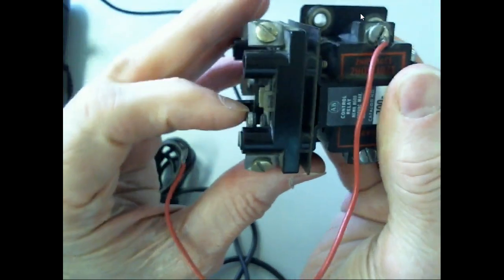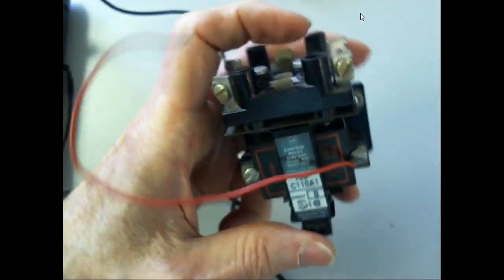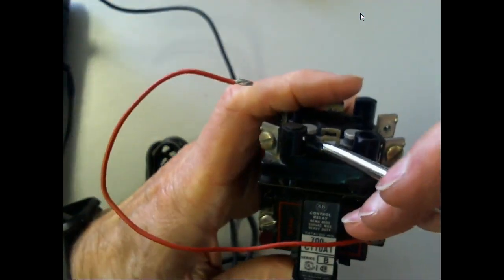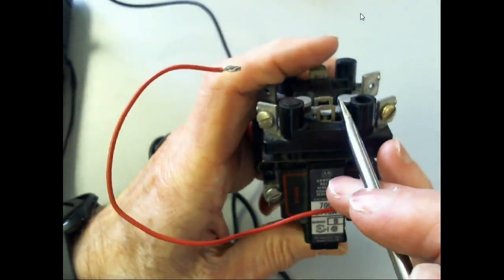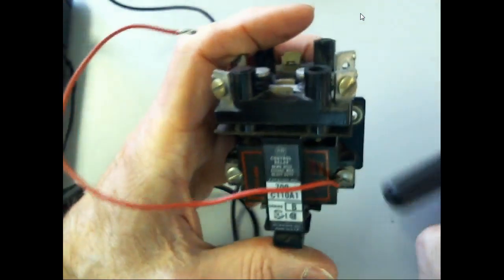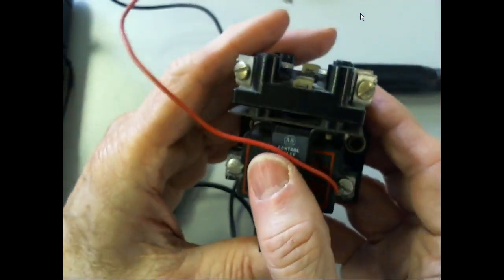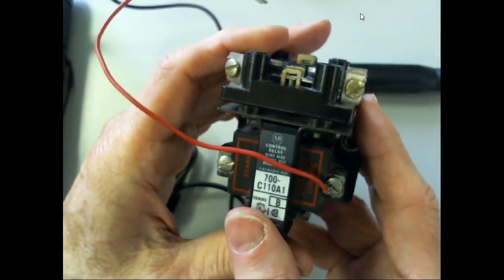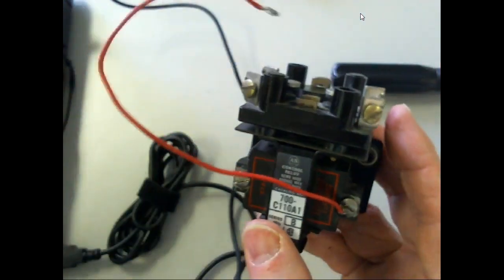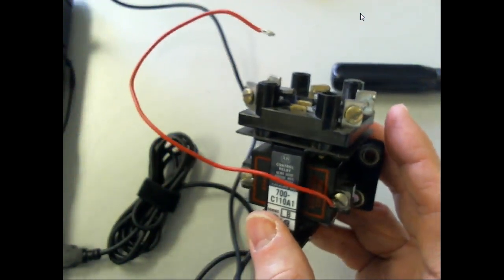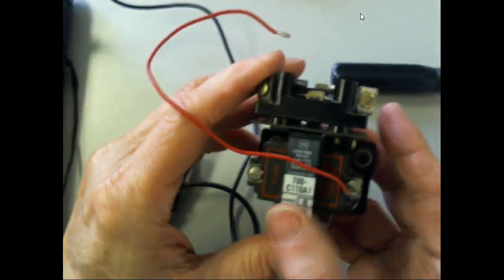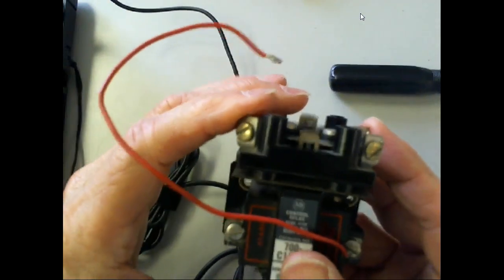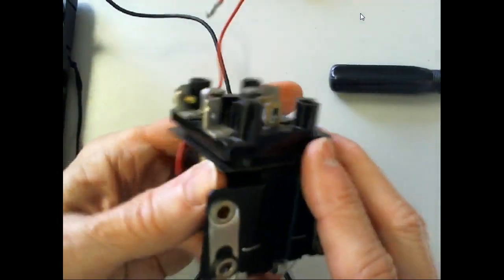And these are double break contacts, and you can actually see the spring on them. So they have the ability to tilt, right? You understand what I'm saying? So what happens if it comes up here and it welds together, and then one side doesn't break? It's going to literally tilt. It's going to help unweld it, right? You understand that? Double break contacts are the most predominant contacts that we use in industry. Even our push buttons are usually double break.